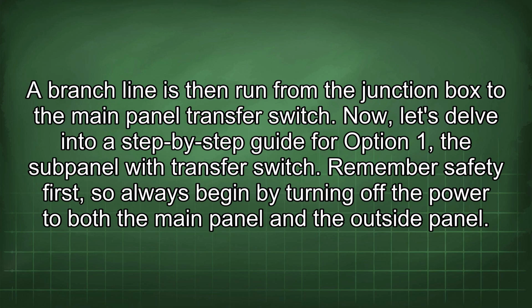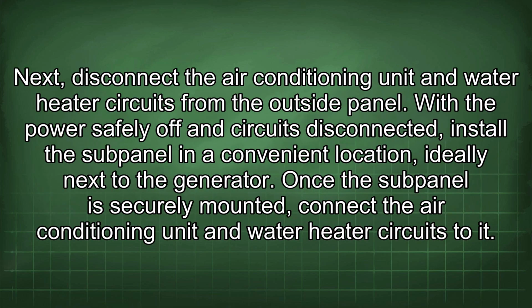Now let's delve into a step-by-step guide for option 1, the subpanel with transfer switch. Remember safety first, so always begin by turning off the power to both the main panel and the outside panel. Next, disconnect the air conditioning unit and water heater circuits from the outside panel. With the power safely off and circuits disconnected, install the subpanel in a convenient location, ideally next to the generator.